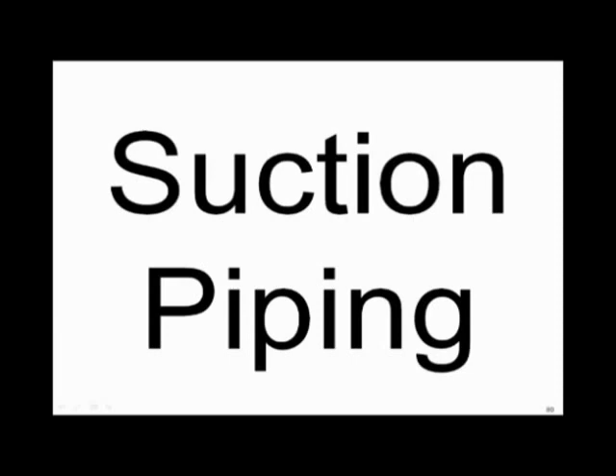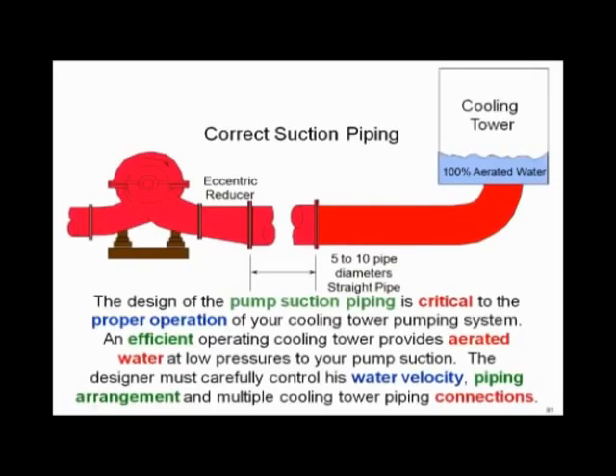Now we'll look at suction piping. Piping is something that we wanted to make sure we looked at and we covered a lot of pieces of it. We're talking about cooling towers, so we've got to look at pumps and a little bit of suction pipe. When you do that, keep in mind that the cooling tower aerates water. So the water in the basin of a tower is full of air. It's full of air as you can get it.